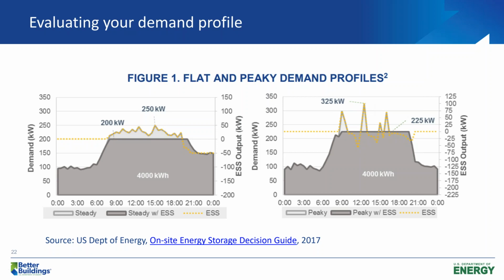You would get more demand cost savings from the right profile than the left profile. That doesn't mean you want a peaky profile if you can help it — you want to manage your loads to minimize those peaks, since that's preferable because you don't want to have to install batteries, it's more cost. But if you can't get around having those demand peaks, then battery storage can result in significant demand savings and higher cost savings than if you had that flat profile.